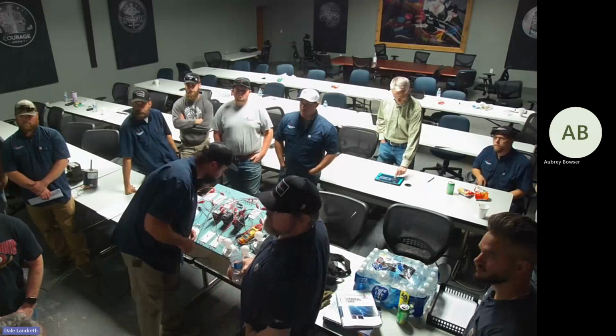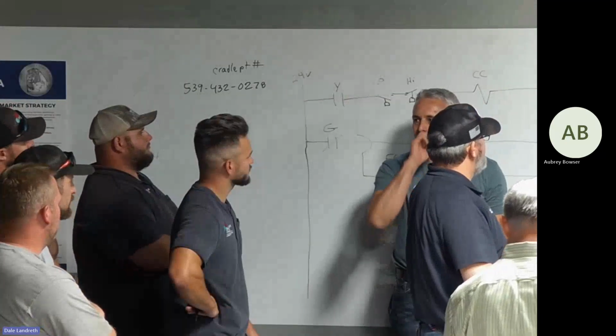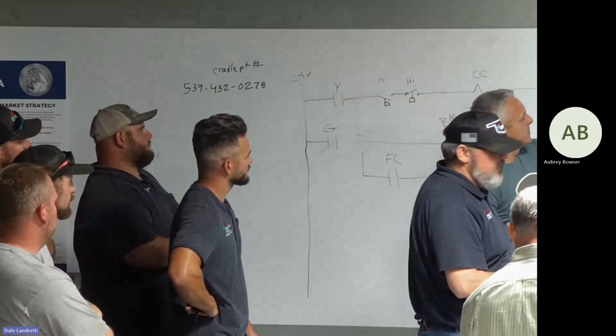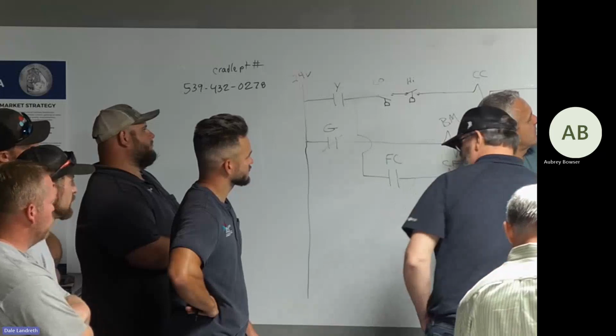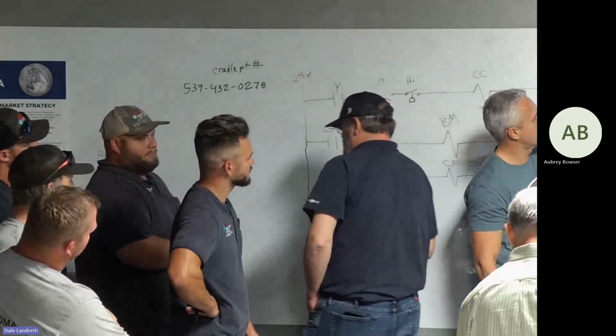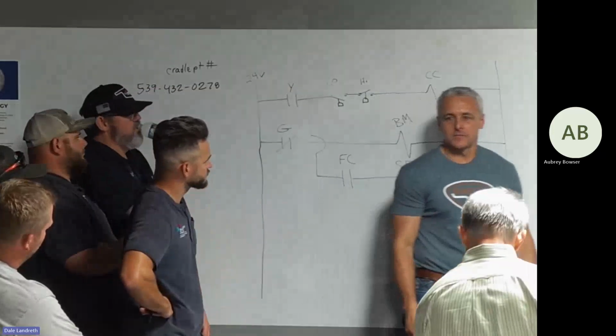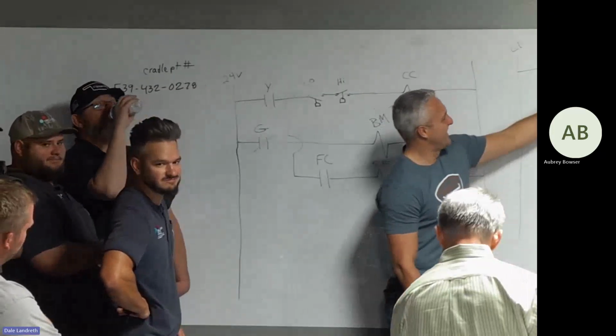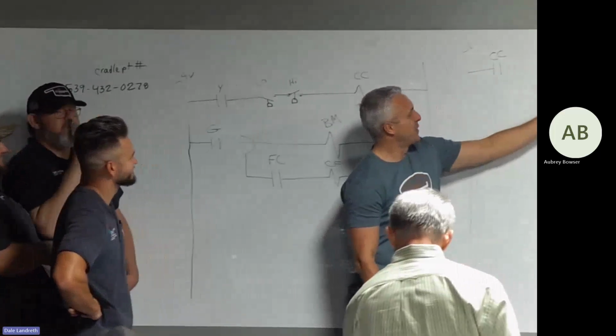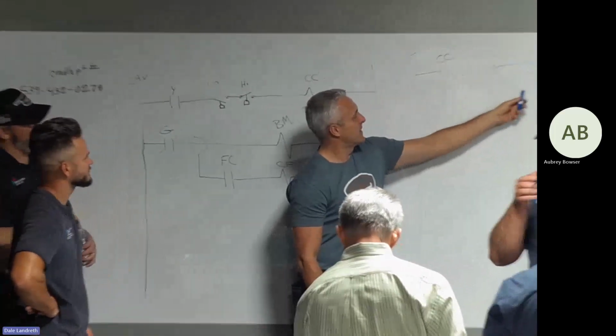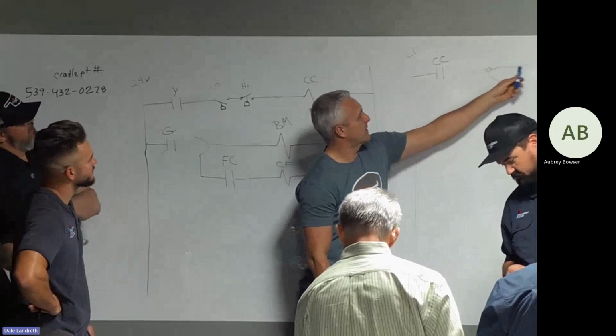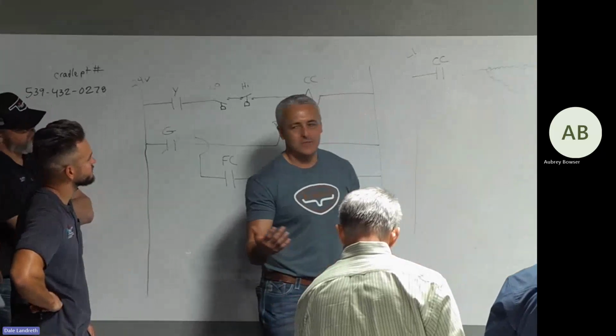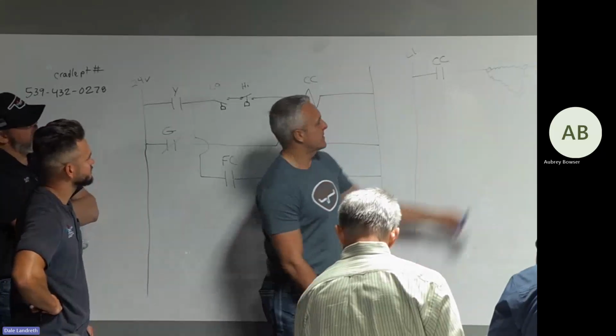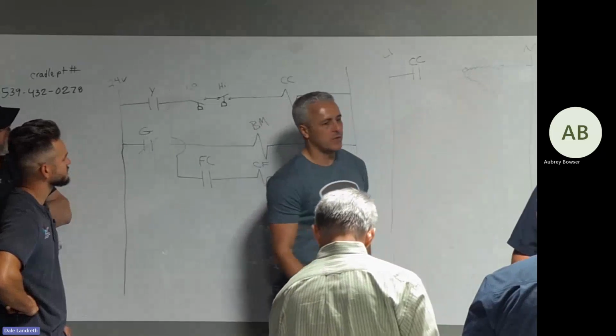So, motor basics, motor 101, which one has the higher resistance? Start. So we'd see a higher resistance in the start winding. If I went here to here with my meters, let's throw a number out there, say 10 ohms. Then I check the other side, go here to here, and I get 6.